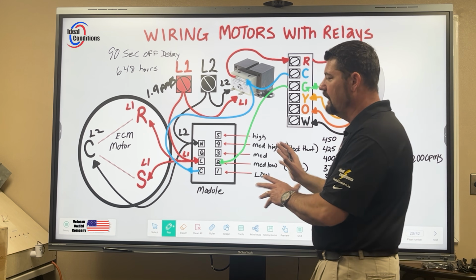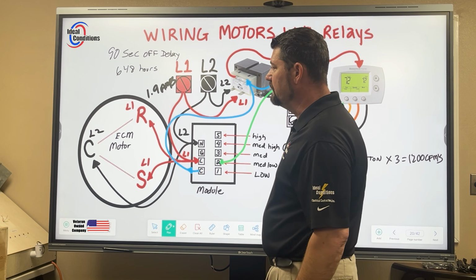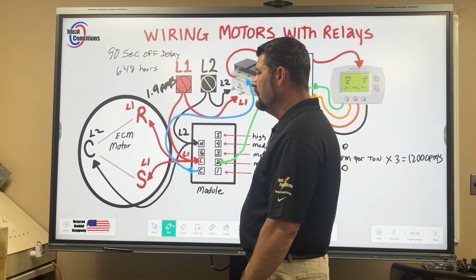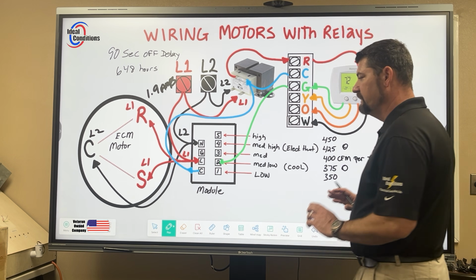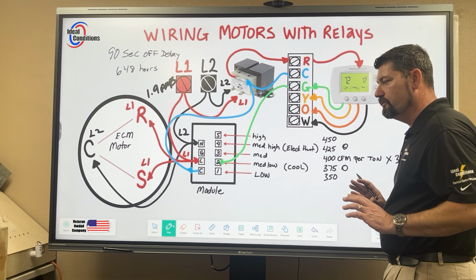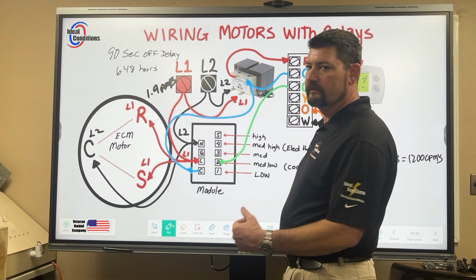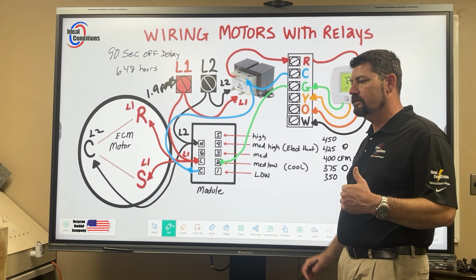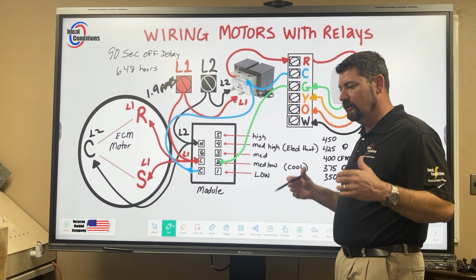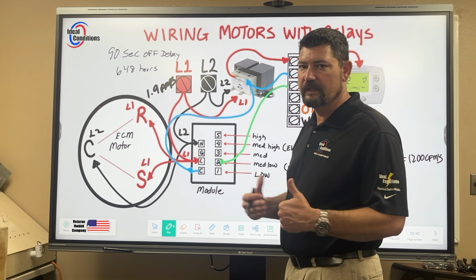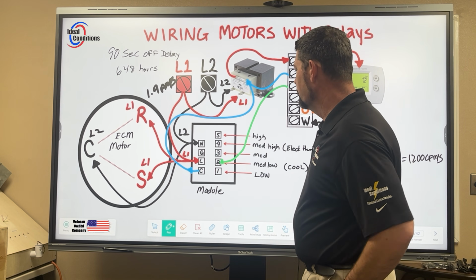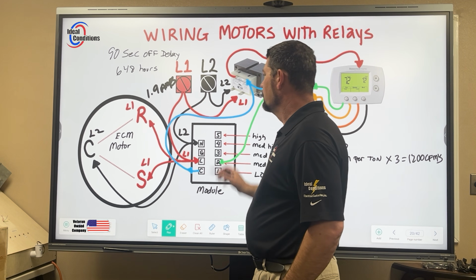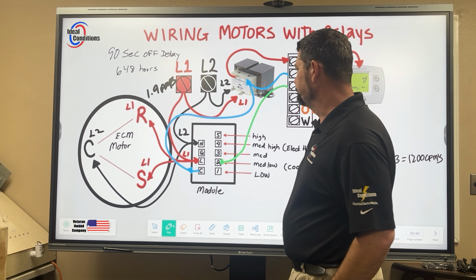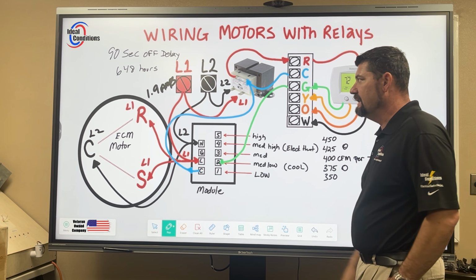So they're not going to let you tamper with that off delay, because these things are tested in a laboratory. These results are governed, very strict. They want to make sure that their equipment is to the factory specifications at all times. And so there is no way of bypassing that. But that's very efficient. That's very good. And they want that 90 seconds.